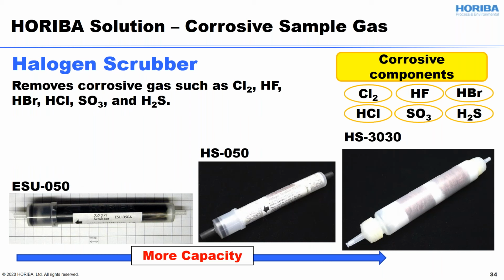And the halogen scrubber, especially in incinerator applications, you need to get rid of this Cl2, HCl, HF, etc. And the halogen scrubber works to remove those corrosive gases. Like I explained, the halogen scrubber model depends on the concentration of the sample gas.